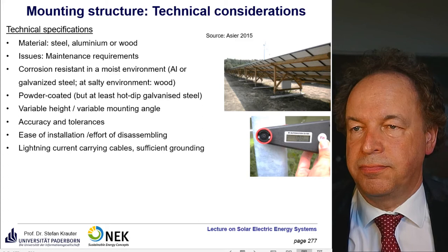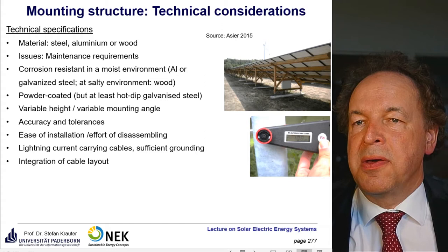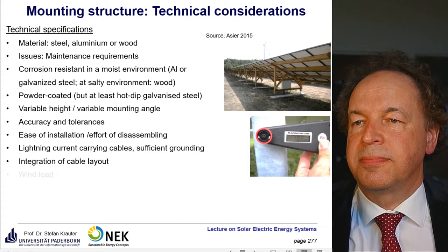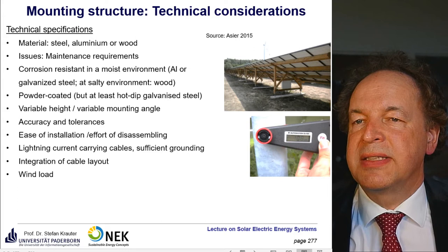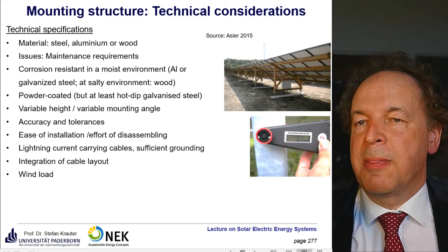Lightning current carrying cables and sufficient grounding. Integration of a cable layout. This depends really on the country. For example, in the United States, you have to carry all cables within a tube, a metallic tube. That's not necessary in Europe. Wind load depends on the locations, but you have to make sure that during the expected lifetime of 20, or nowadays more like 30 years, even the heaviest storm will do no damage to the structure.